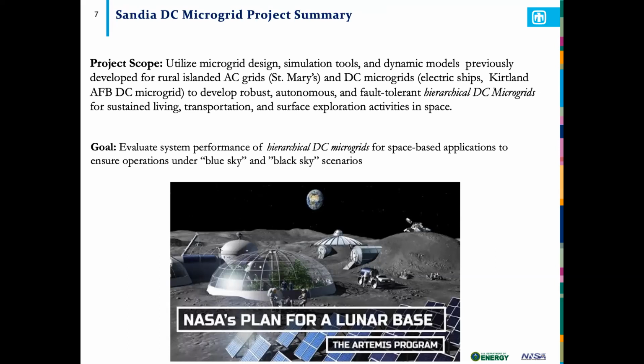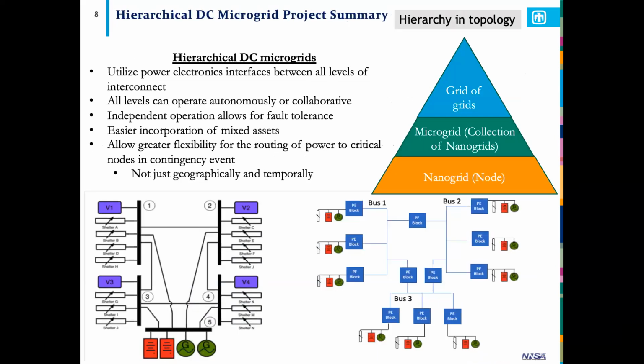So what do I mean by hierarchical microgrid? A typical high resilience microgrid is what you'd see on the left here, with a central bus with generation and unidirectional power flow to different nodes that all contain loads. This is compared to a hierarchical microgrid, shown on the right, which has generation, load, and storage at each node, with power electronics interconnecting each node.